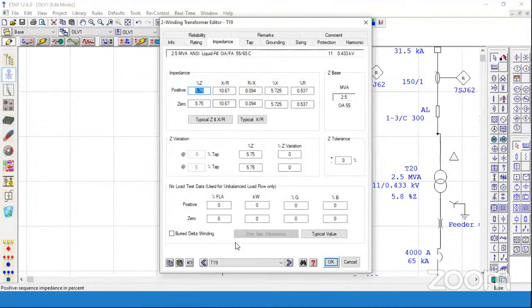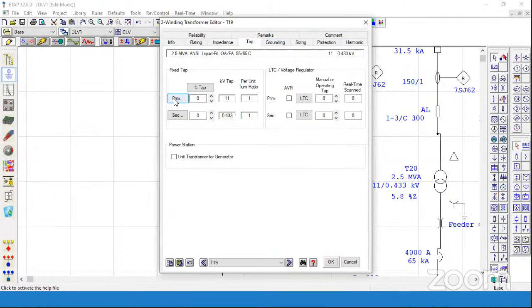We only need to give the rating of voltage as well as the MVA rating of the transformers, and its impedance level. If we are in a designing purpose, that is for a greenfield plant, then we don't have any exact parameter values, so we can assume the typical parameters. But in order to have an accurate result, we need accurate data, which will be available from the nameplate, and those parameters have to be placed over here. Then the tap position, whether the transformer is on load tap changer or off load tap changer, we can also give as input in this section.